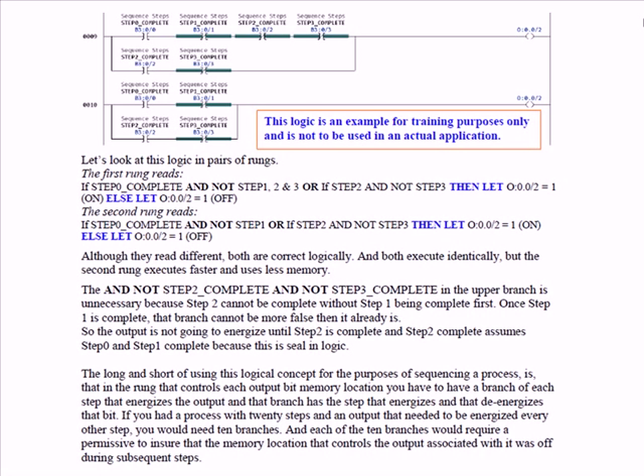In the second ladder of the first rung, rung 9, when step 2 is complete and not step 3, then we turn on output 2 again. And then when step 3 is complete, both ladders of that single rung - in other words, both ORed sets of permissives - are false and output 2 is off.